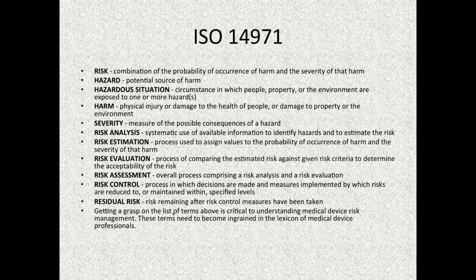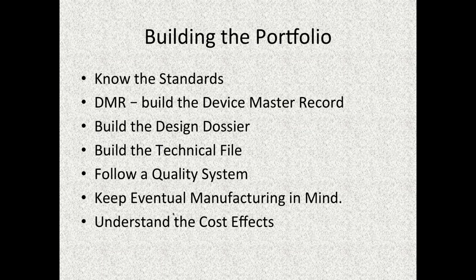ISO 14971, I just put down kind of a summary here of what they require. It is very similar to the FDA, so it requires us to go through each one of these elements of the risk associated with every aspect of the device. Build a portfolio, know the standards, build a device master record, build what's called a design dossier. This is going to be everything that you've researched, everything that has to do with the safety or efficacy of this product or your submission. Anything that I would put in there, all your marketing stuff as well, anything you found out about the market size in your research. Follow a quality system early on.